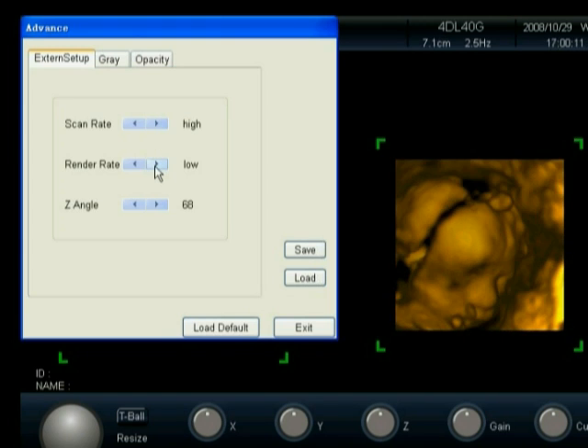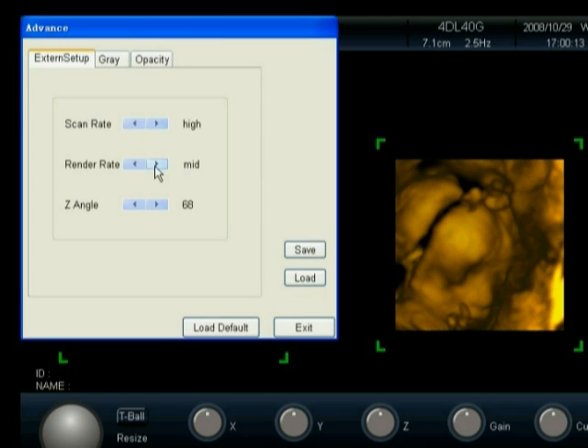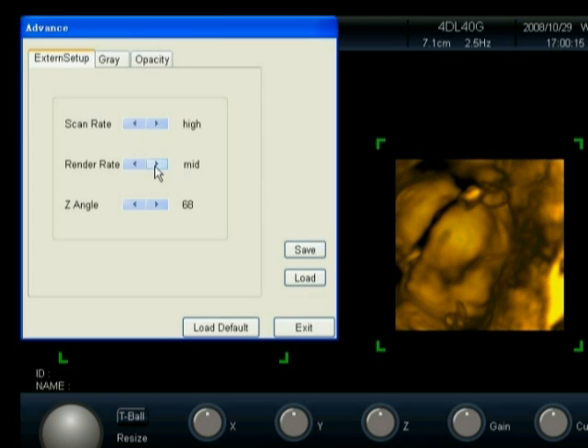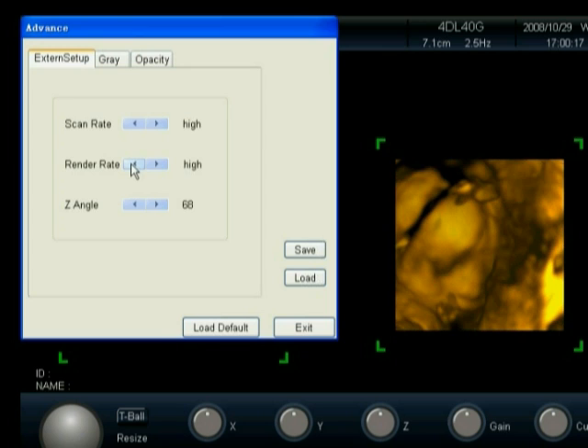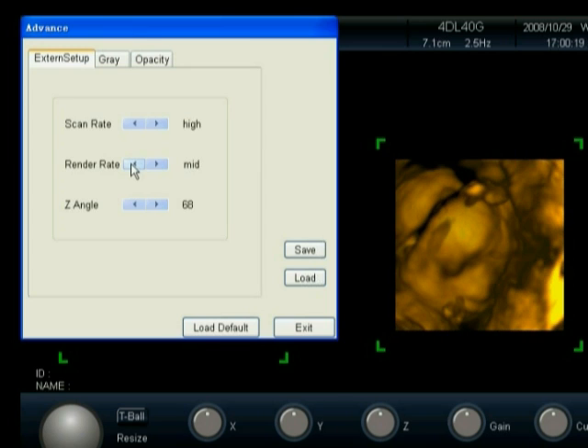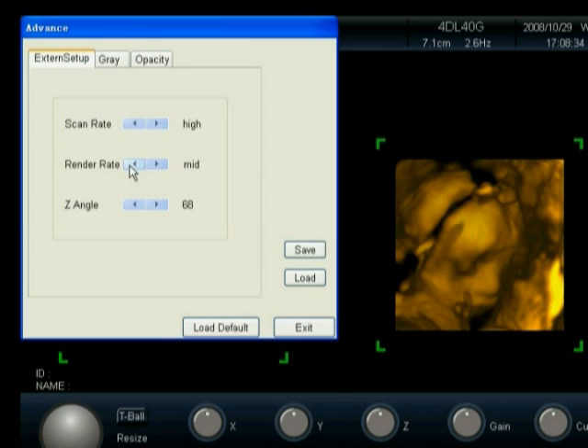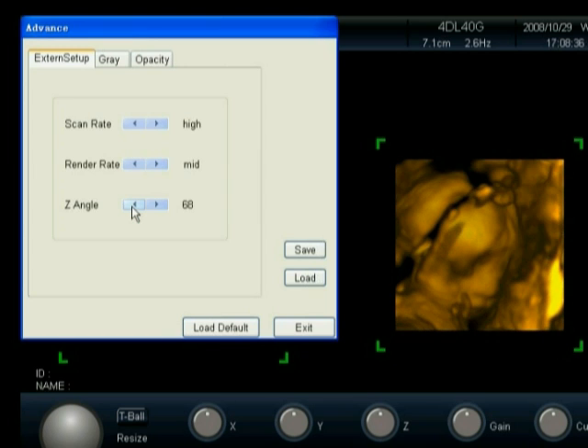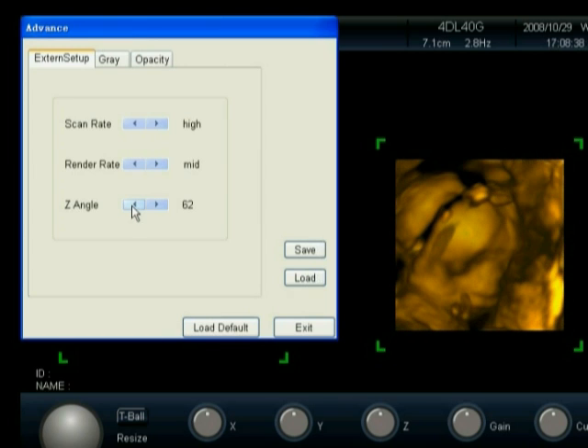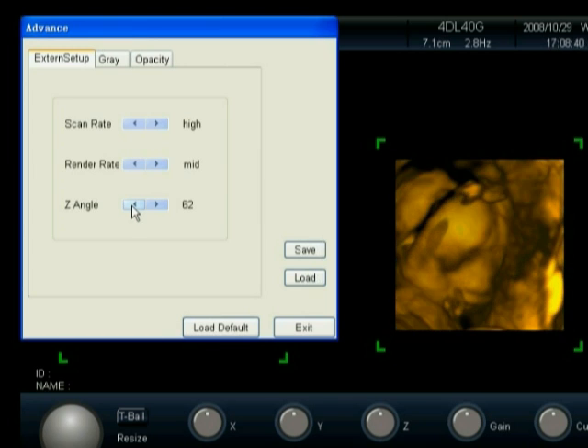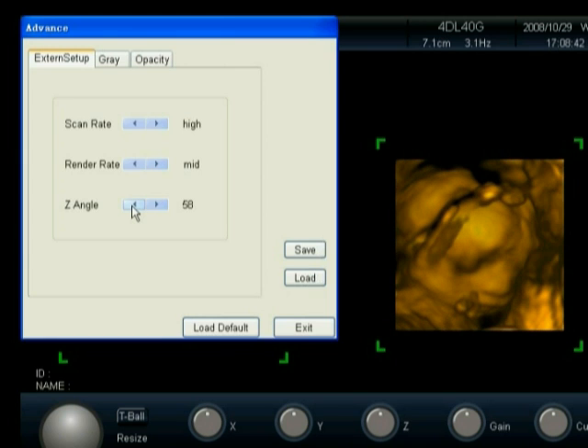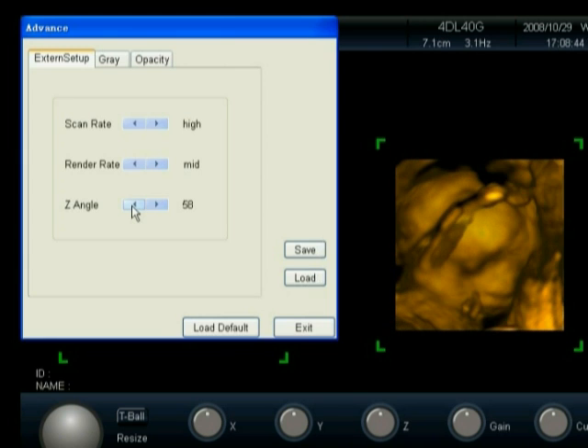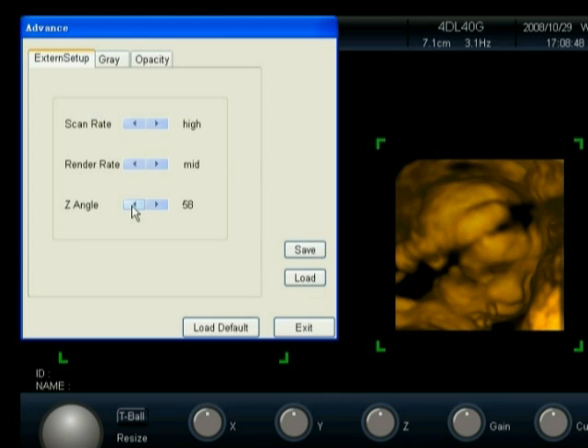Increasing rendering speed will improve the relevant system speed in 4D mode, but the imaging quality will be lowered a little bit. It is recommended to use medium rendering speed. A decrease in scanning angle along axis Z will improve 4D image real-time performance, but the image acquisition range will decrease. If you want to observe the fetal face, usually the Z angle can be set between 50 and 60 degrees.